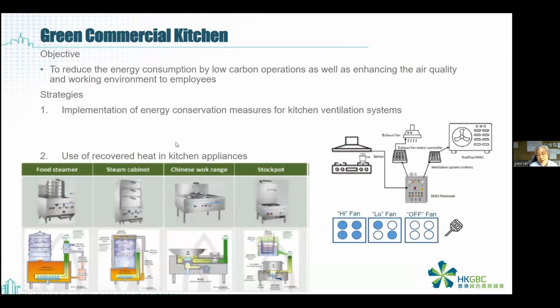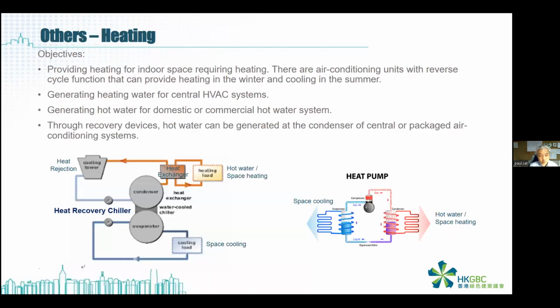And for some kitchens, they use heat recovery kitchen appliances, so that when the waste heat comes out, they recapture the waste heat to heat up the water, so that the water becomes preheated before it is directly boiled by the boilers or the fuel, something like that. And the other thing is that we also use heat recovery chillers or heat pumps to provide instantaneous cooling and heating together.